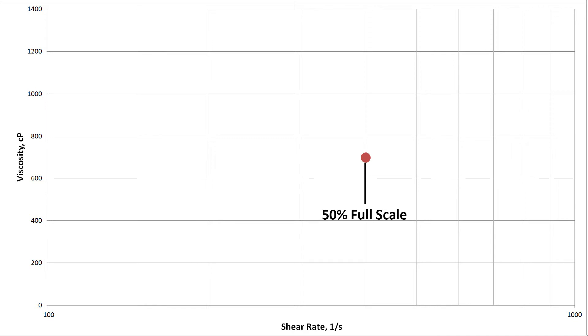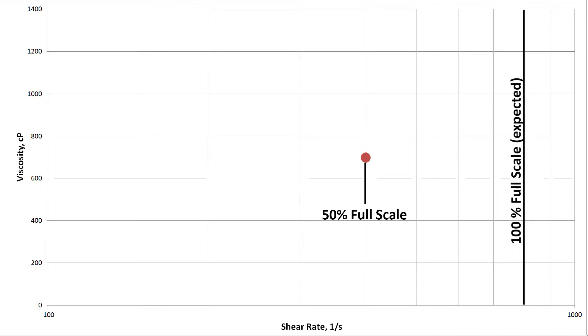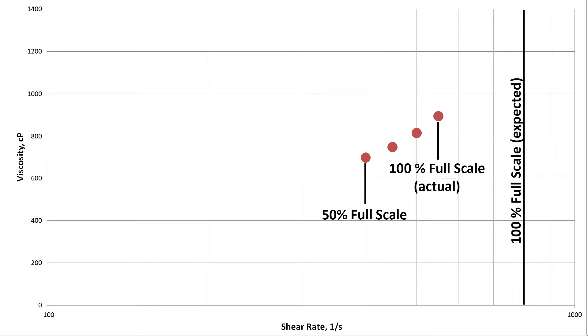Shear thickening samples are less common, but in essence will reduce your available shear rate range due to the opposite behavior. Be careful when increasing shear rates with a shear thickening sample. Increase the shear rate in small increments to avoid overpressuring the chip.